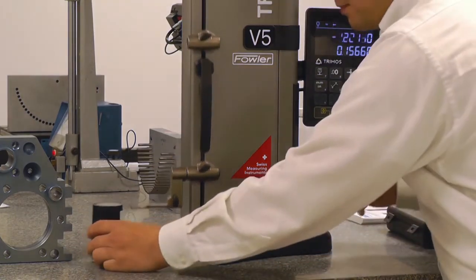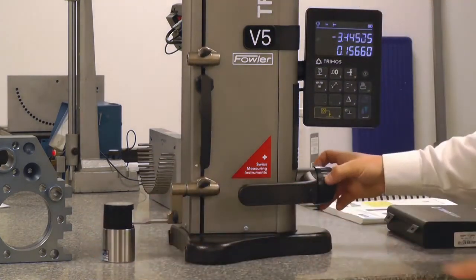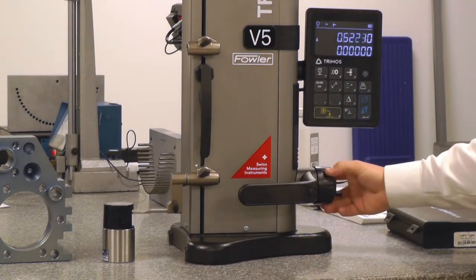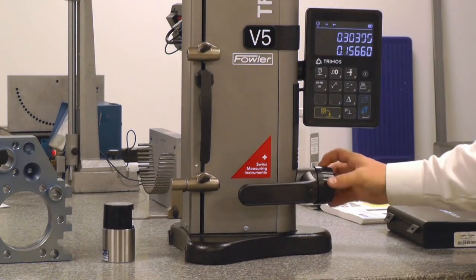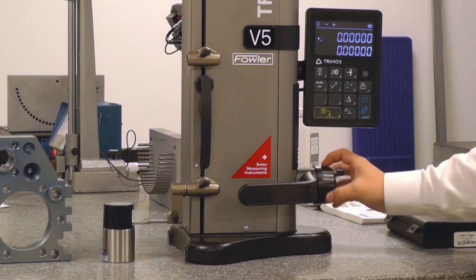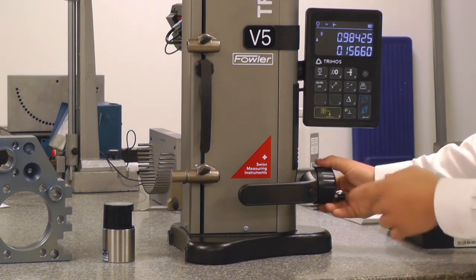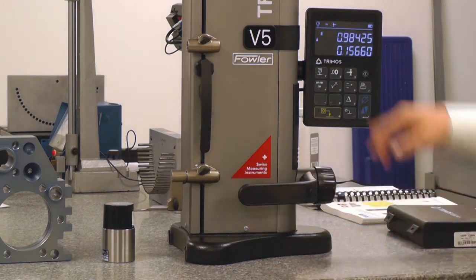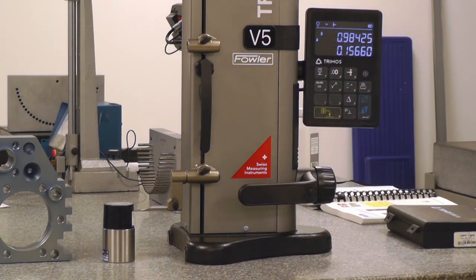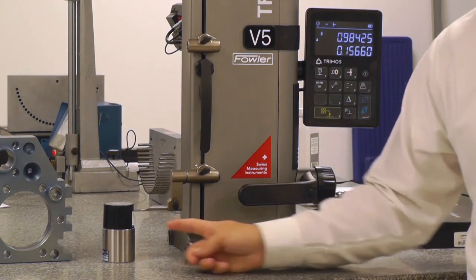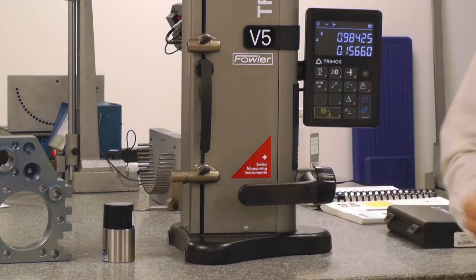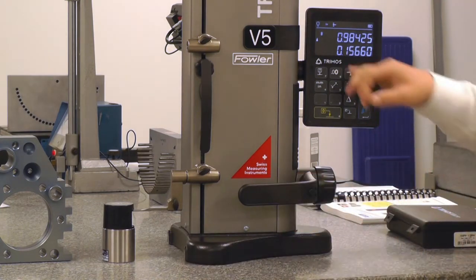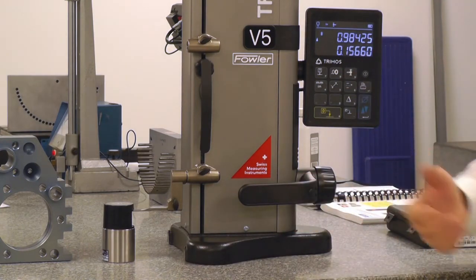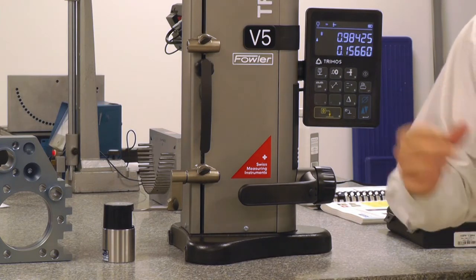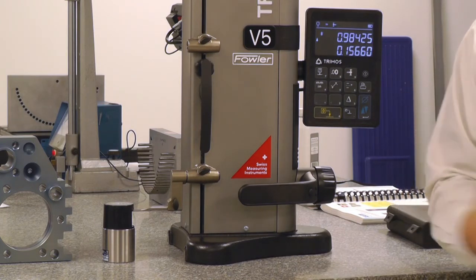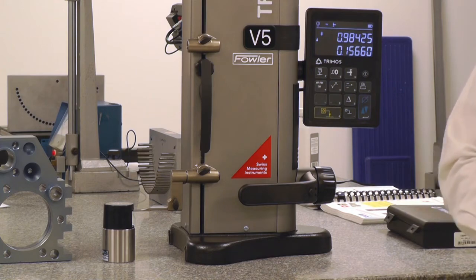So when we come down here to master our probe, we're going to engage the probe down and up, and then we'll repeat that process. And if we leave our probe engaged at our final contact, you're going to see we have 0.98425 of an inch. We are using a 25 millimeter master, which is 0.98425 of an inch. And on our second display here, we have 156 thousandths, which is the diameter of the probe that we are using. Effectively, we're using a 4 millimeter probe.